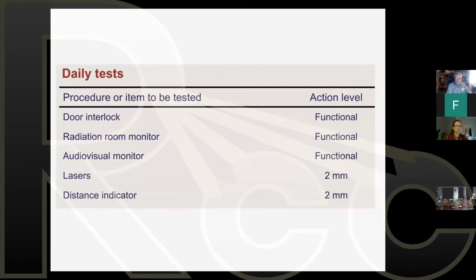As I mentioned, the door interlock must be tested daily and has to work. In the United States, there is a requirement, even for linear accelerators, that there has to be a radiation room monitor. It must flash red when the beam is on. It seems a little silly, I know. It's an electronic machine. It's not cobalt. The source isn't going to get stuck in the on position, but many states still require a radiation monitor to show when the beam is on.